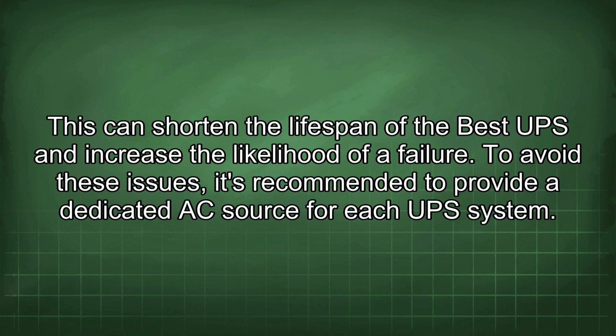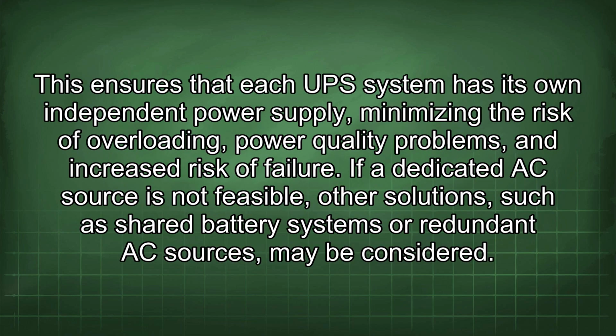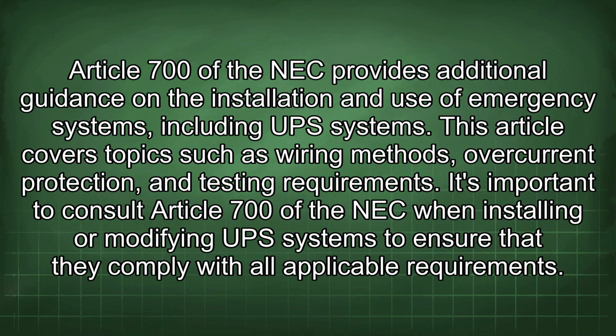To avoid these issues, it's recommended to provide a dedicated AC source for each UPS system. This ensures that each UPS system has its own independent power supply, minimizing the risk of overloading, power quality problems, and increased risk of failure. If a dedicated AC source is not feasible, other solutions, such as shared battery systems or redundant AC sources, may be considered. Article 700 of the NEC provides additional guidance on the installation and use of emergency systems, including UPS systems. This article covers topics such as wiring methods, overcurrent protection, and testing requirements.